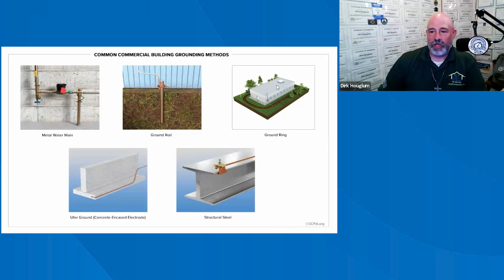Here's your grounding rod as seen before. The grounding ring is common, especially around pools, because pools have to be grounded very carefully—water is a good conductor of electricity flow, though it does have some resistant qualities. People can get electrocuted in a pool if it isn't grounded properly. Mike Holt has a good video testing this, where he energized the ground in his pool and was able to swim fine, but once he got out and put one foot in a different area, he actually got electrocuted.